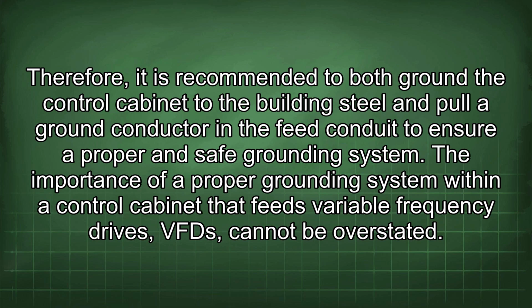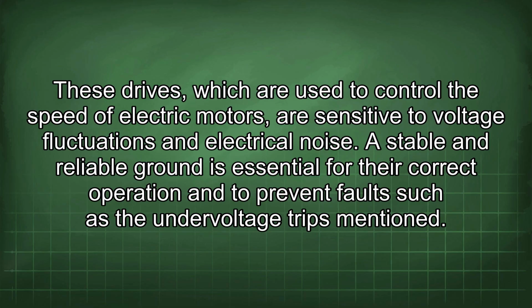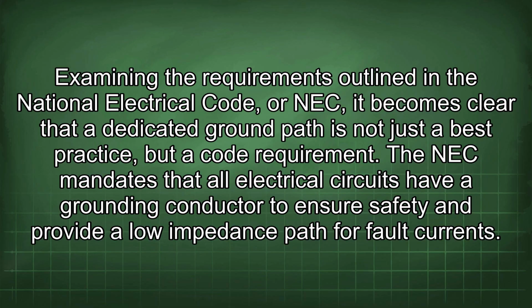The importance of a proper grounding system within a control cabinet that feeds variable frequency drives, VFDs, cannot be overstated. These drives, which are used to control the speed of electric motors, are sensitive to voltage fluctuations and electrical noise. A stable and reliable ground is essential for their correct operation and to prevent faults such as the undervoltage trips mentioned. Examining the requirements outlined in the National Electrical Code, or NEC, it becomes clear that a dedicated ground path is not just a best practice but a code requirement.